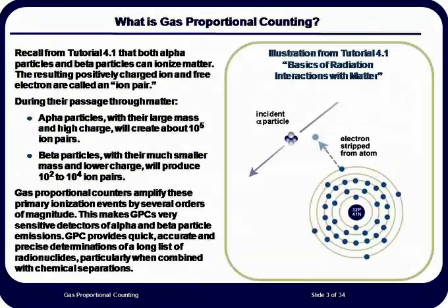The higher the charge on the particle, the larger will be the ionization per unit distance traveled. The higher the mass of the medium that makes up the detector, the larger the electron density is, and thus there will be a greater number of ionizations per linear path length of the particle. If we combine these two concepts, ionization capability and detector material density, we find that using a gas like argon as a detector will provide very good sensitivity to the ionization characteristics of alpha and beta particles and poorer response to gamma radiation.